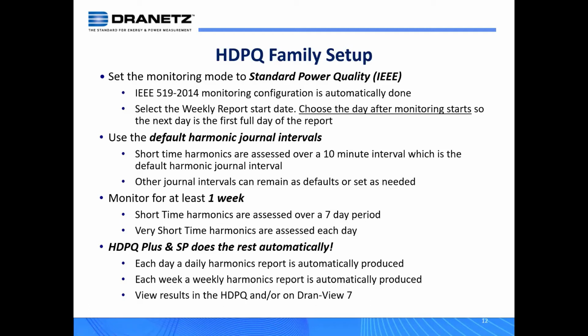at least 1 week. But if you keep the instrument recording for, let's say, a month, you'll get 4 of these intervals, 1 for each week of the month. And then you'll have daily reports for very short time harmonics for each of the 7 days during that week. All right. And again, as I said before, the HDPQ Plus and the SP does everything automatically for you. There's nothing else that you need to do.